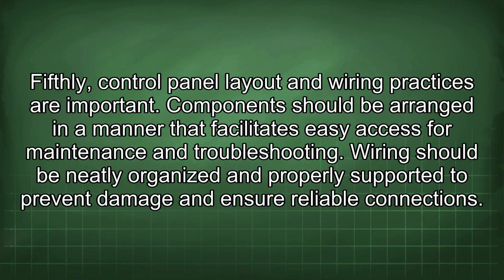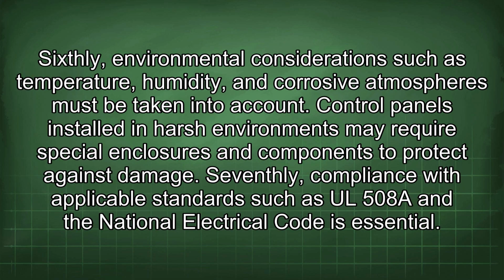Components should be arranged in a manner that facilitates easy access for maintenance and troubleshooting. Wiring should be neatly organized and properly supported to prevent damage and ensure reliable connections. Sixthly, environmental considerations such as temperature, humidity, and corrosive atmospheres must be taken into account. Control panels installed in harsh environments may require special enclosures and components to protect against damage.